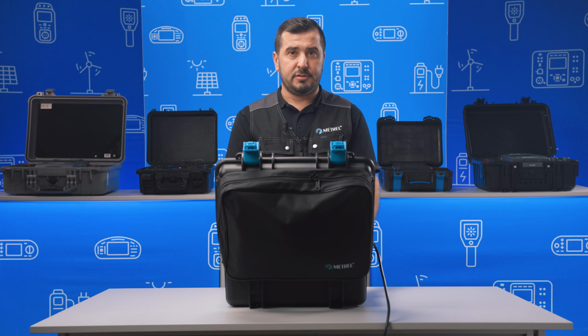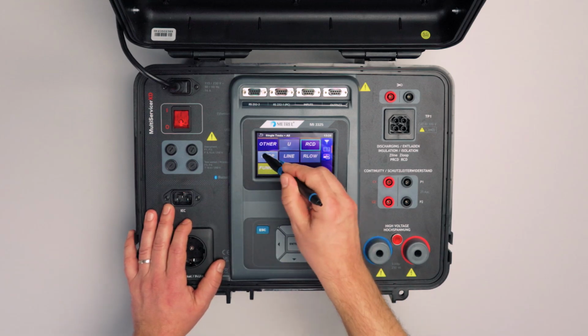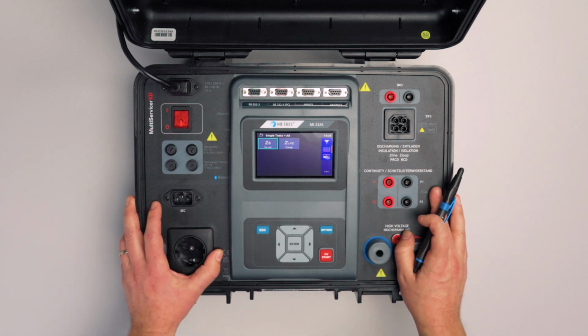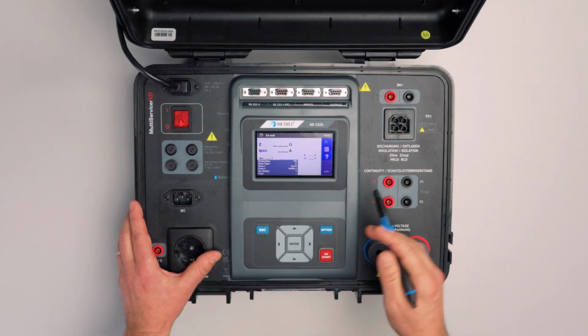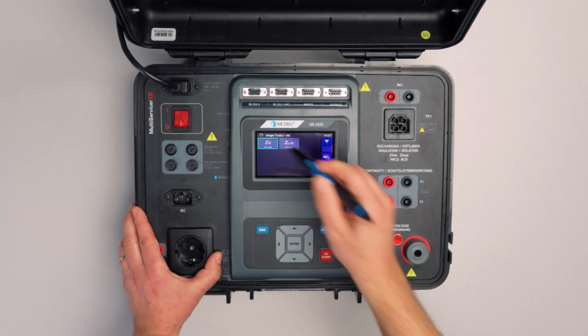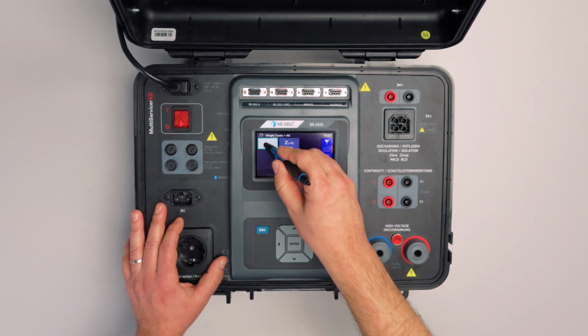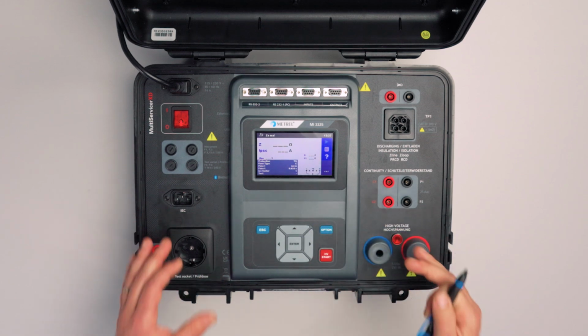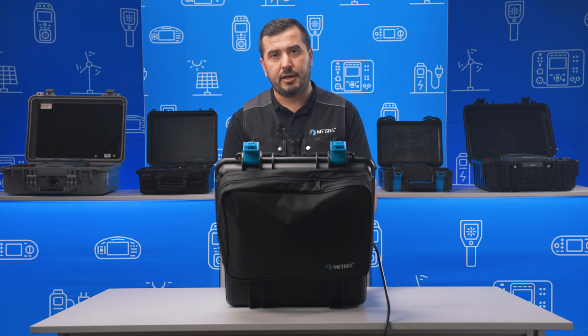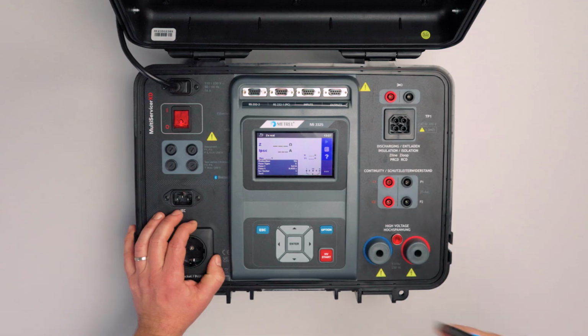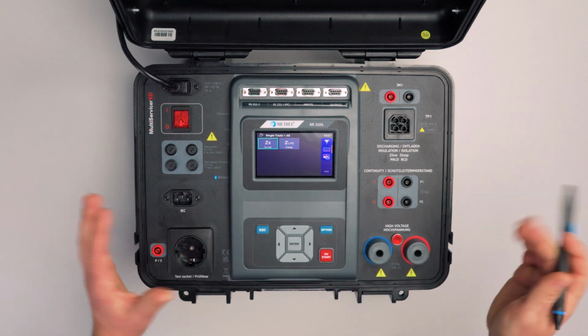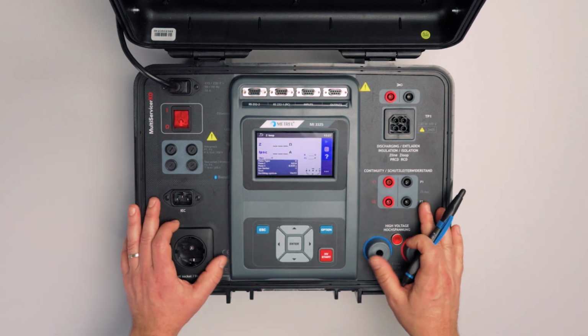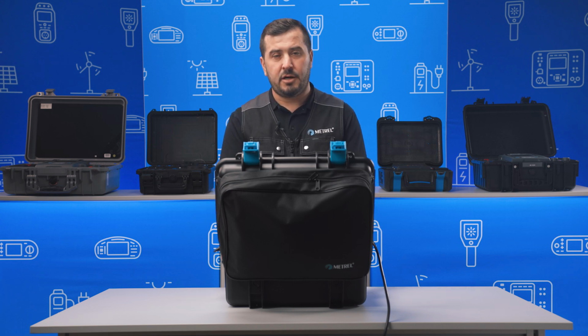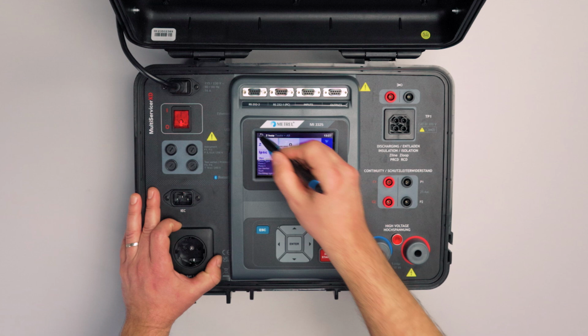Then, for the electrical installation safety part, we have the measuring functions for testing the resistance of the fault loop, in case we have RCD protection or in case we do not have RCD protection in our installation. The difference between these two functions is that with RCD protection the instrument will perform the test with a lower current and will not trip our RCD out. When using the normal Z-loop function, the instrument will of course apply a higher current. The measurement is a bit more precise and faster.